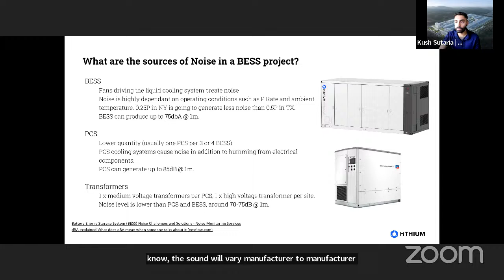The PCSs can be louder, not just cooling systems, but as Darrell mentioned, tonal noise as well, and humming from electrical components. So although they generate more noise, you have less of them on a site because you generally have 3 or 4 BESS per PCS.